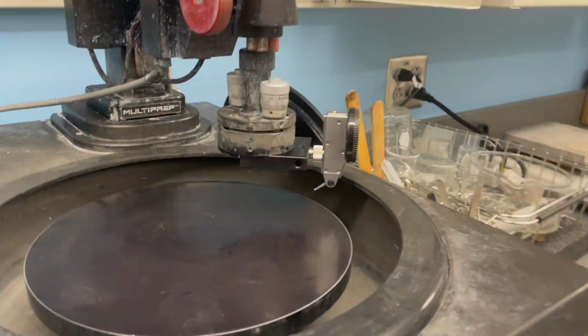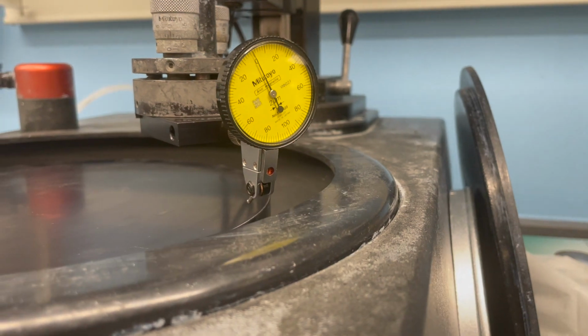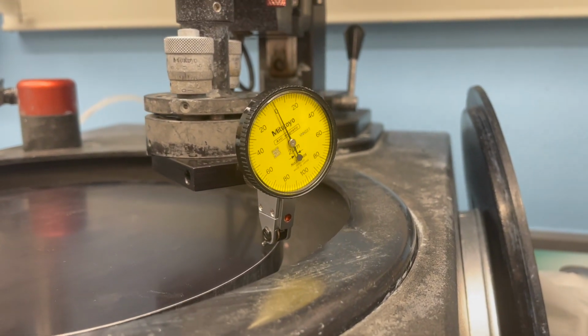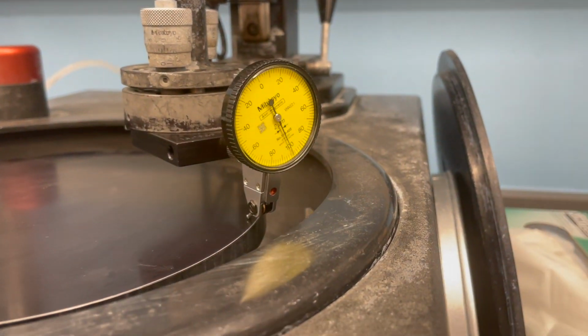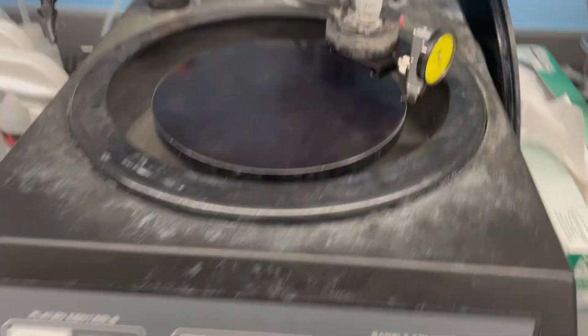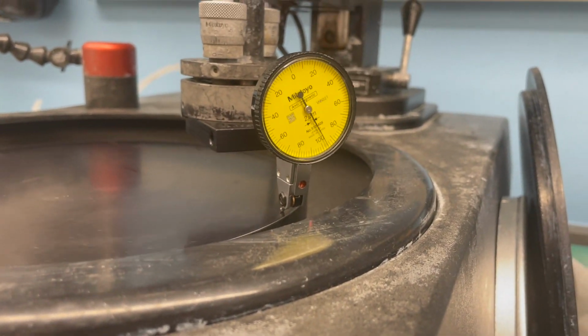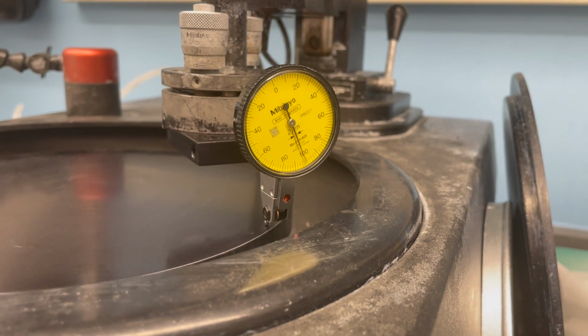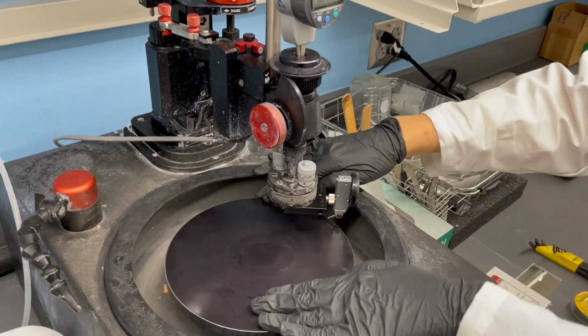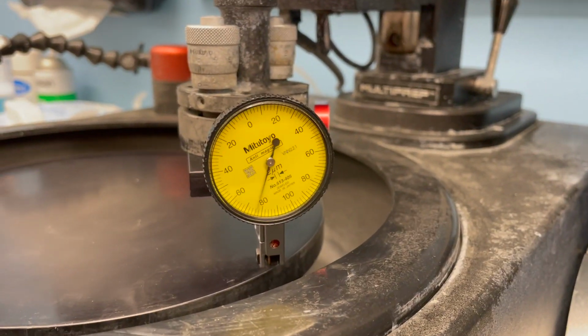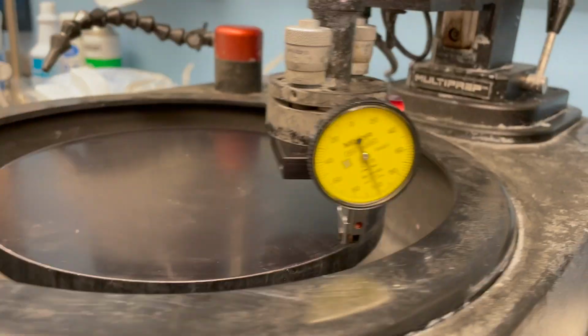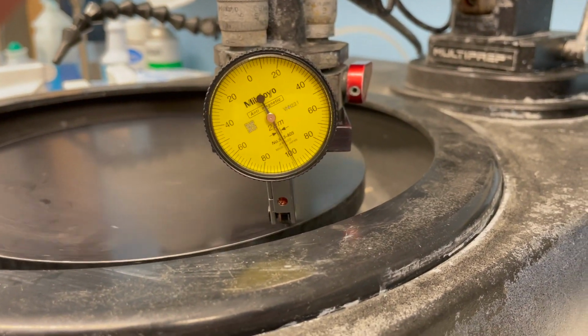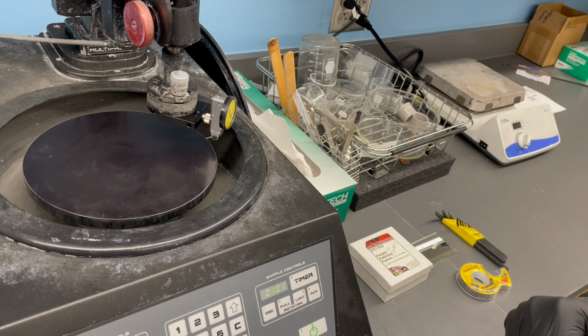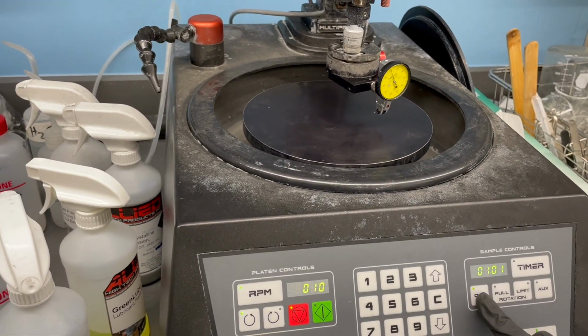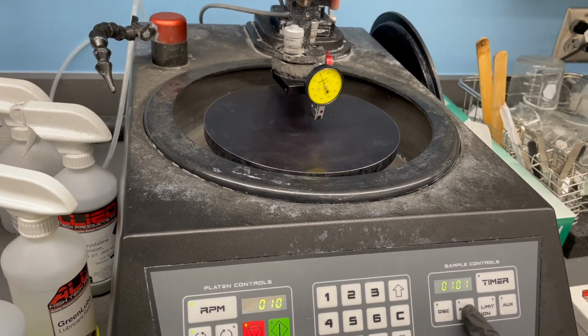Once the dial is on the edge, press the oscillate button to stop the arm, then lower the arm until the dial reads 100. Press the green button to rotate the platen and make sure the dial remains within 2 step sizes of 100. If it deviates too far, raise the arm and wiggle the platen, then repeat the last step. Now we will calibrate the arm. Raise it back up and use the oscillate button to bring the arm back to the center of the platen.